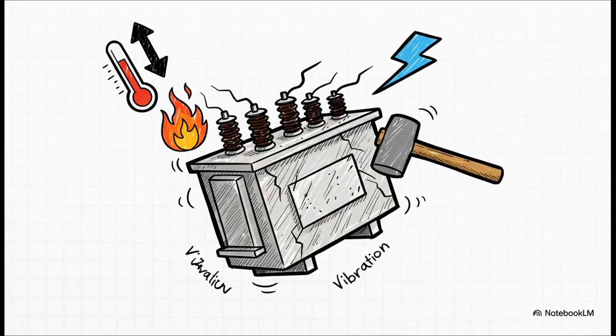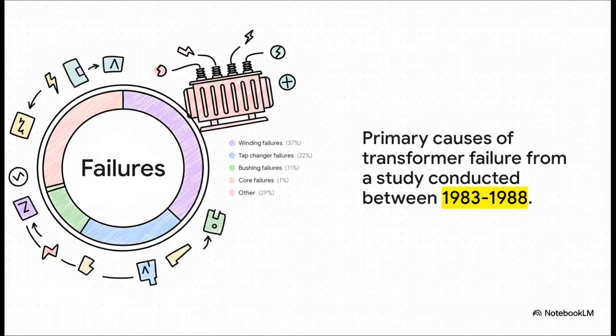Yeah, transformers really live a tough life. Every single day, they're physically expanding and contracting as they heat up and cool down. They're constantly vibrating. They get hammered with huge electrical punches from faults happening somewhere else on the grid. Throw in overheating from high demand and random voltage surges, and you've got a device under constant assault. When you look at the data of how they fail, a really clear picture starts to emerge.